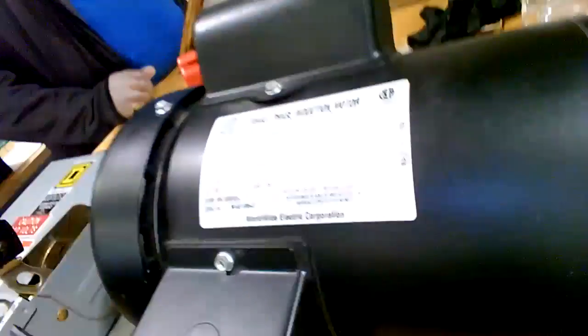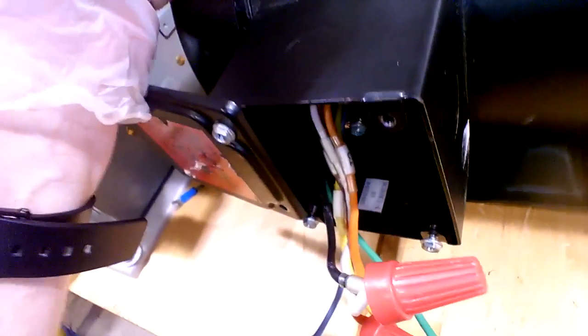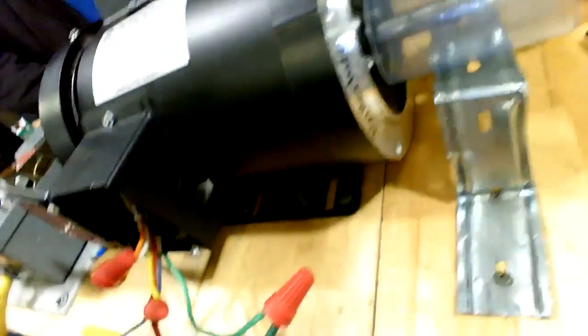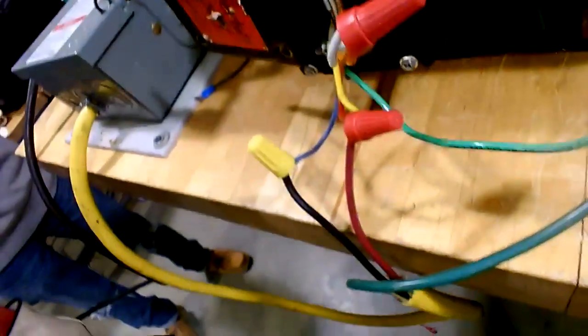Or the windings on the inside can start shorting out. When they do, it's going to draw too many amps. So we'll get into that stuff later, but basically, for whatever voltage you're running at, low or high, you go up under it, and there's a correlating amp rating that you should be no more than, when it's at top speed. Now start up, it starts up higher. You can see the inrush, it'll be higher when you start it up.